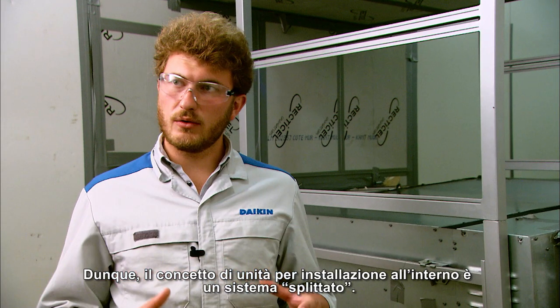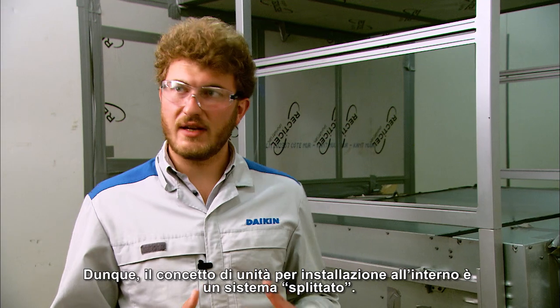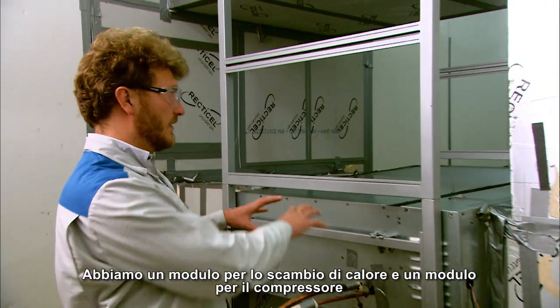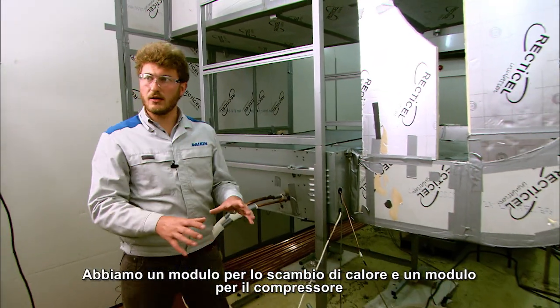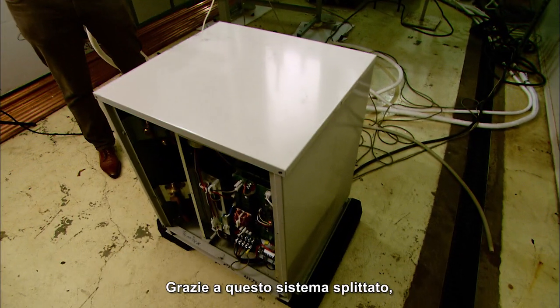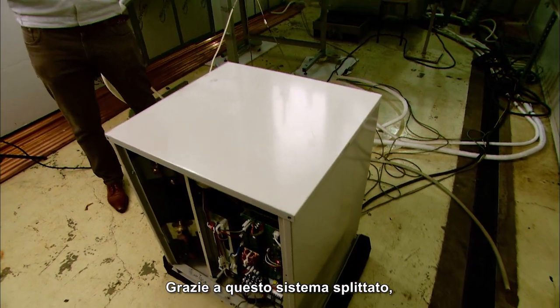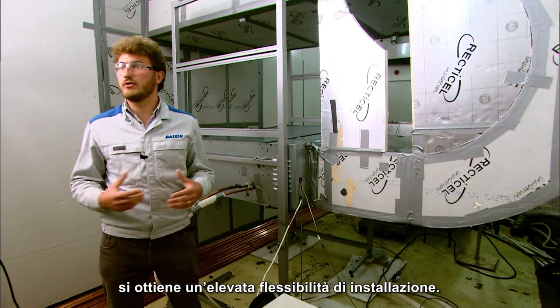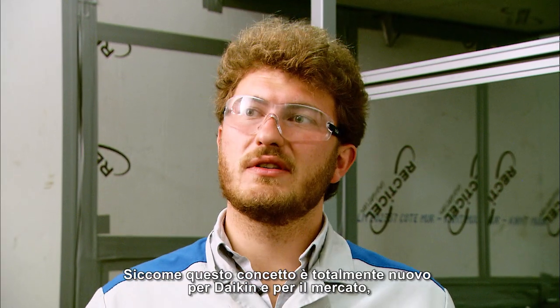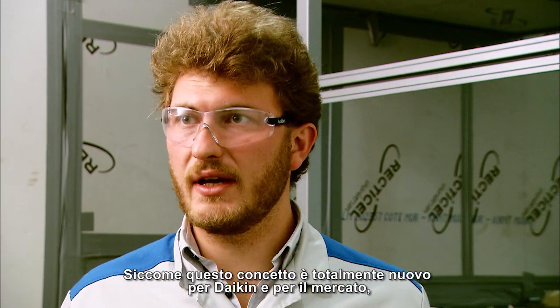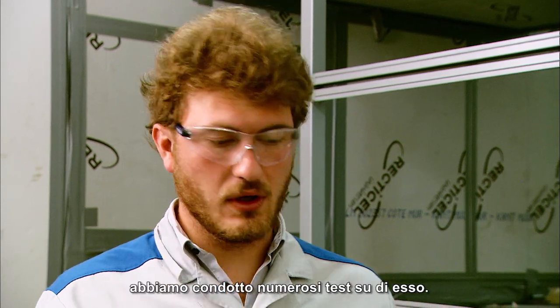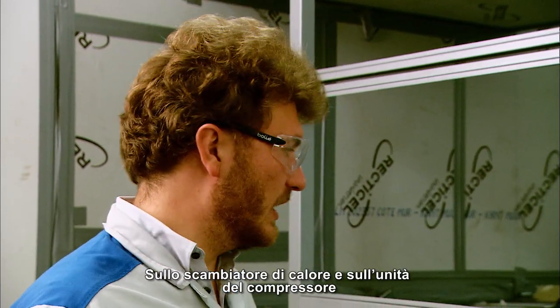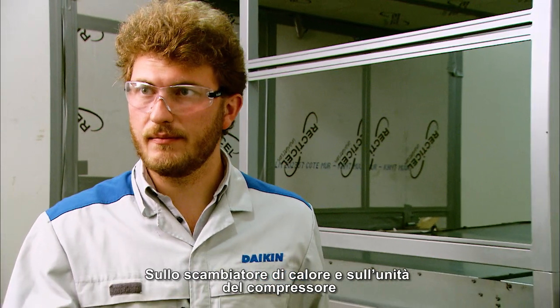So this outdoor for indoor concept is a split system. We have a heat exchanger module and a compressor module. Due to this split system, it offers huge flexibility during installation. Because this is a totally new concept for Daikin and the market, we performed a lot of tests on this unit, on the heat exchanger and on the compressor system.